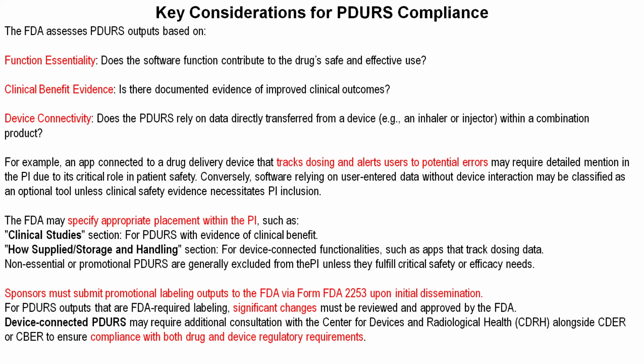So if they have another device as a companion, like in respiratory healthcare the inhaler, or the injectors in diabetes, they usually have a companion software. So it depends on how the combination of the products looks. This is another thing you should think about if you ever come up with a device. Here you should have in mind that a device is not just hardware, right? It can be software. Medical device software is considered a device.